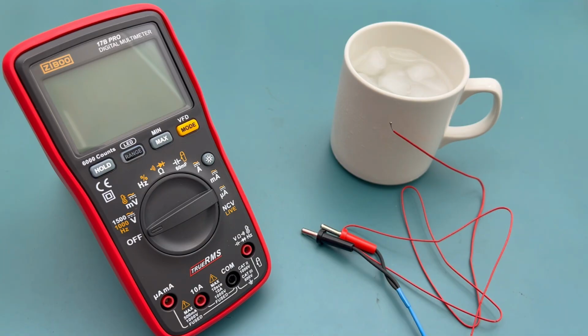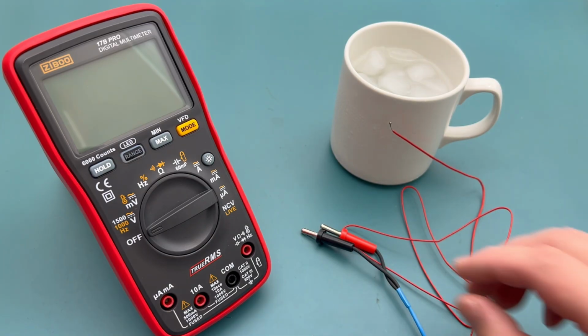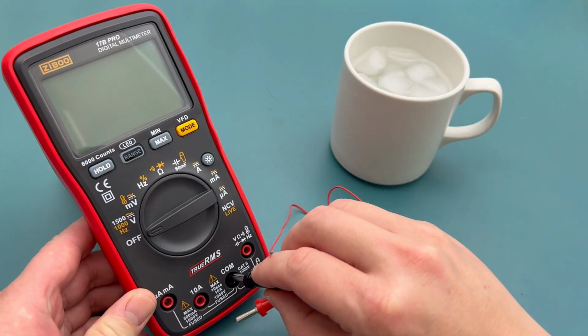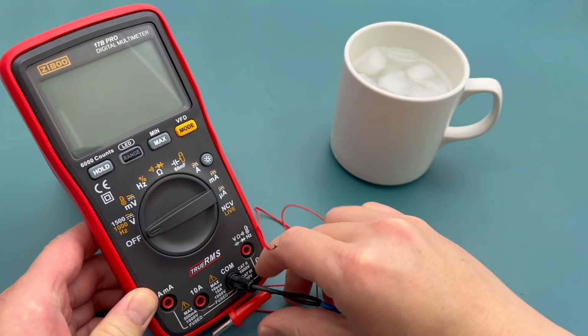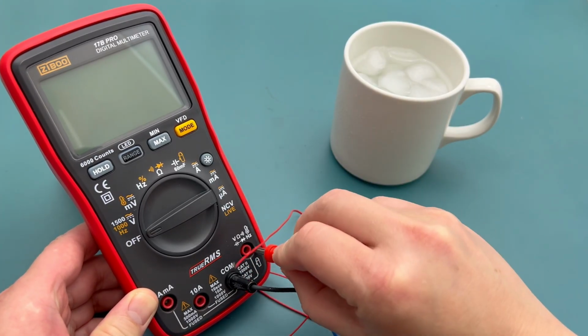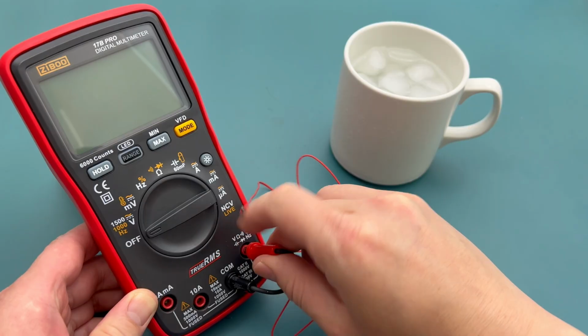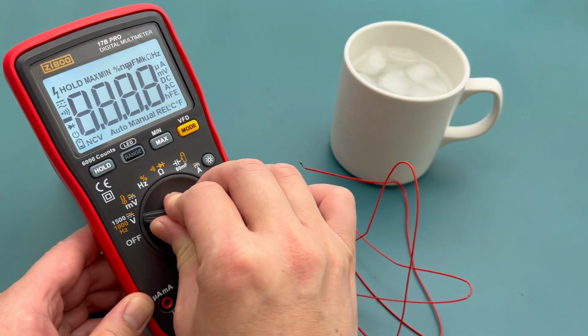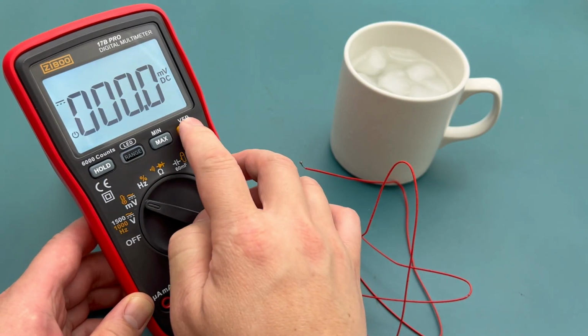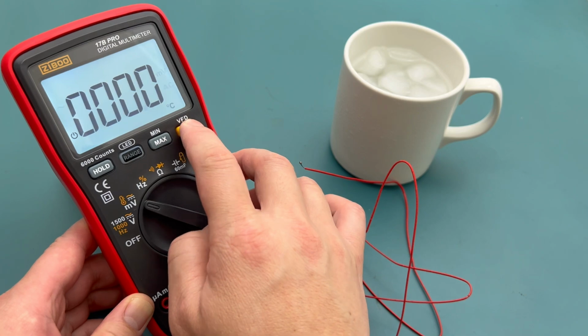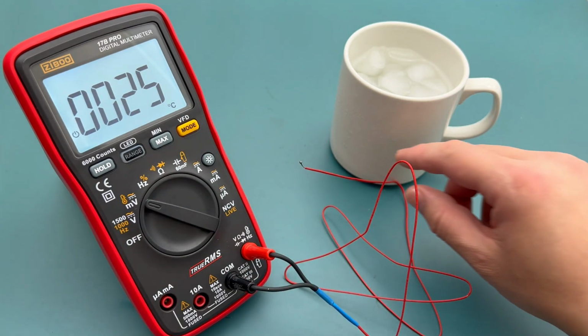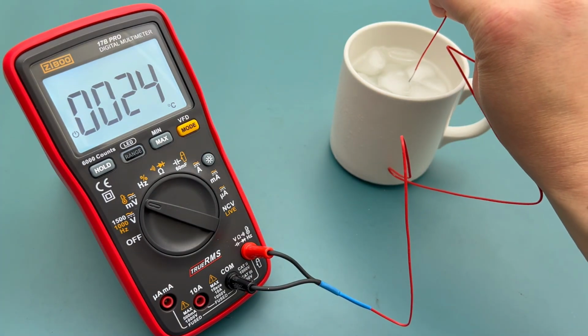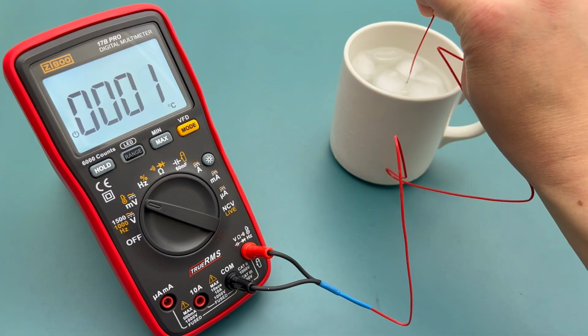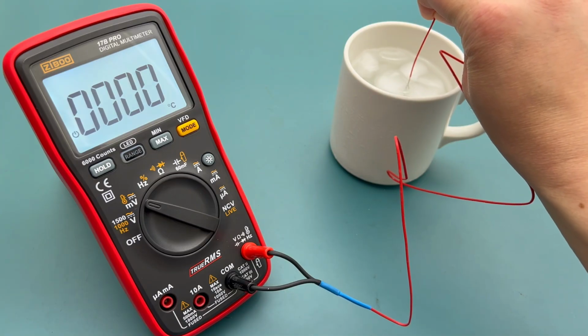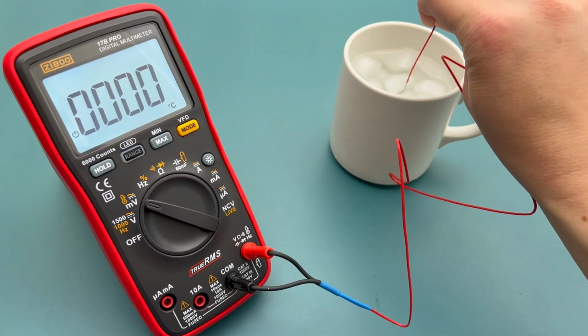The next test is to measure the temperature of this ice water. For this test, we need to use a thermocouple. Insert the black connector to the COM port. Insert the red connector to the voltage temperature port. Turn the dial to the millivolts setting. Press mode to switch to the temperature setting in Celsius. The display shows 0 degrees Celsius, as expected for ice water.